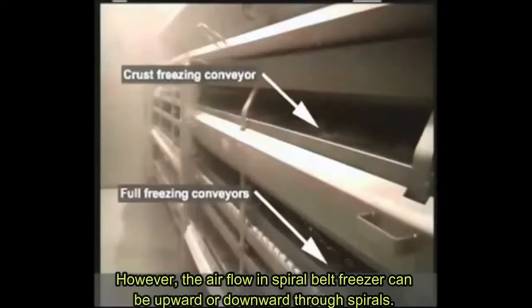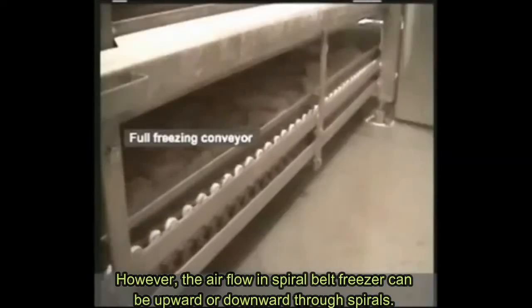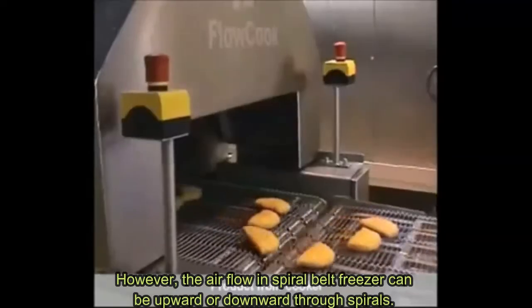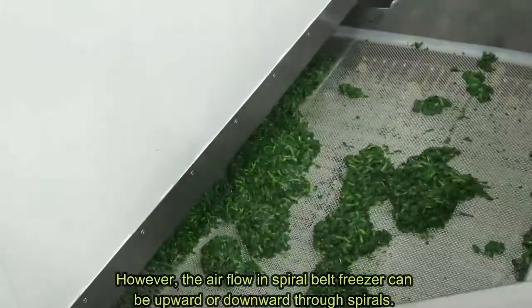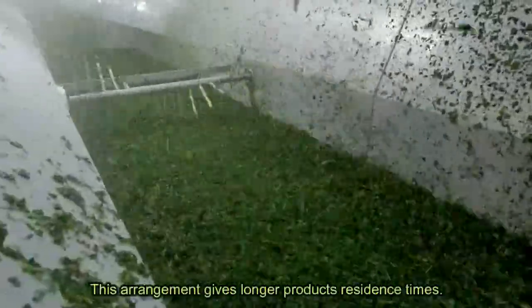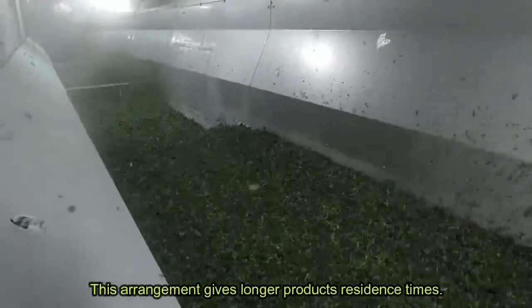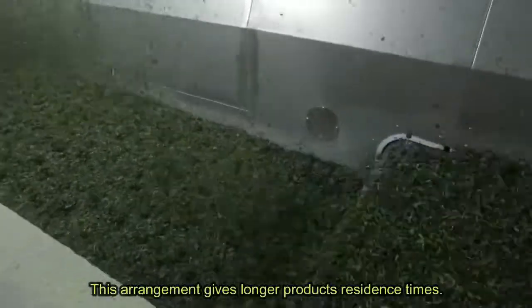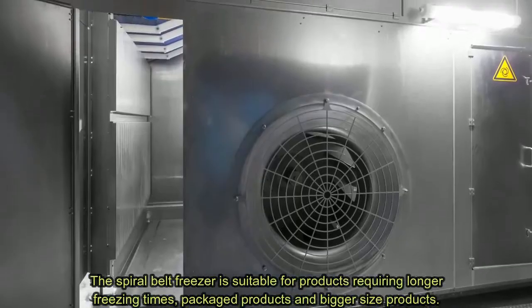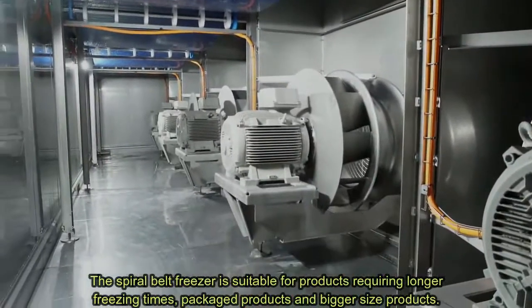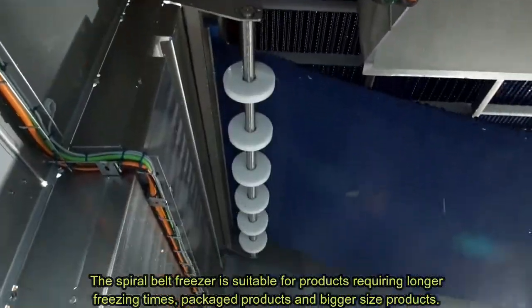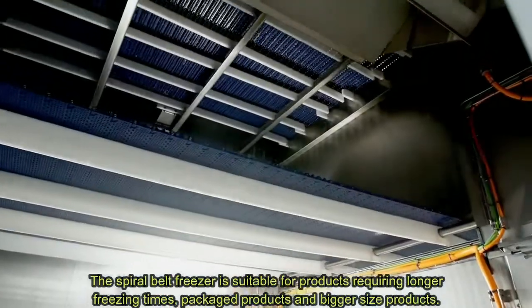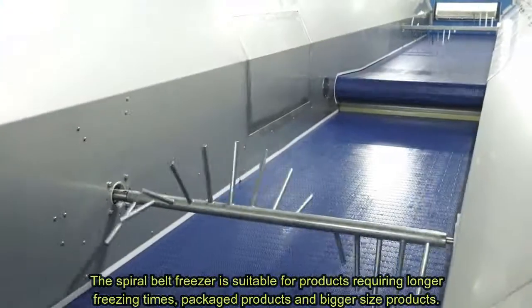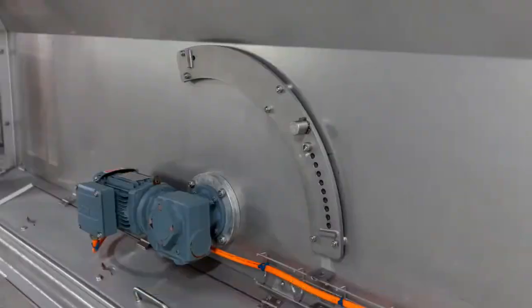However, the airflow in a spiral belt freezer can be upward or downward through the spirals. This arrangement gives longer product residence times. The spiral belt freezer is suitable for products requiring longer freezing times, packaged products, and bigger size products.